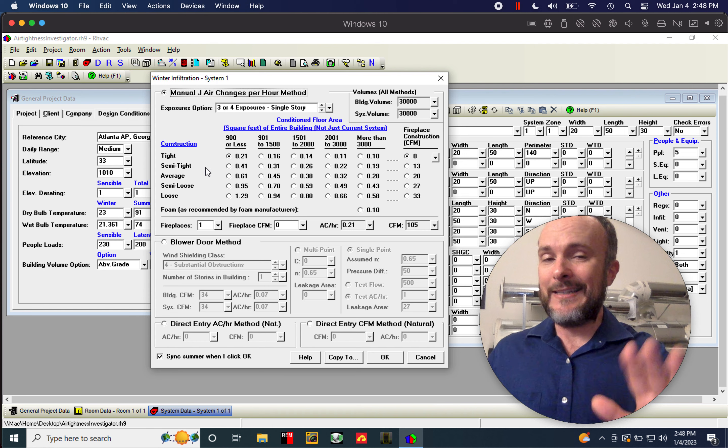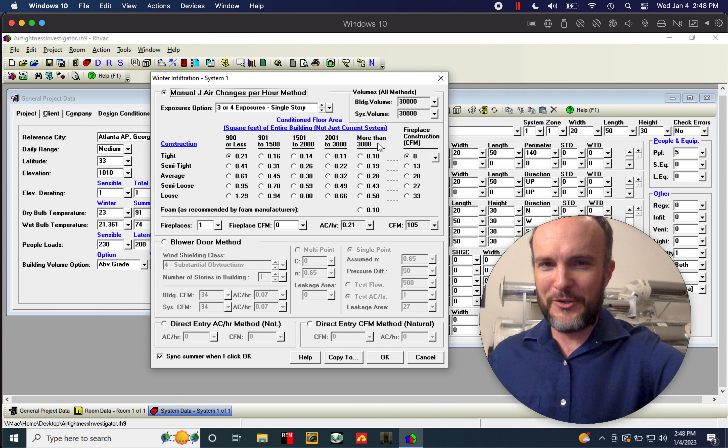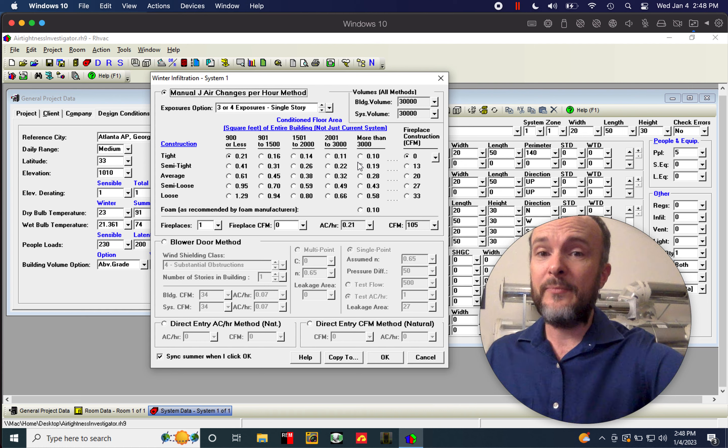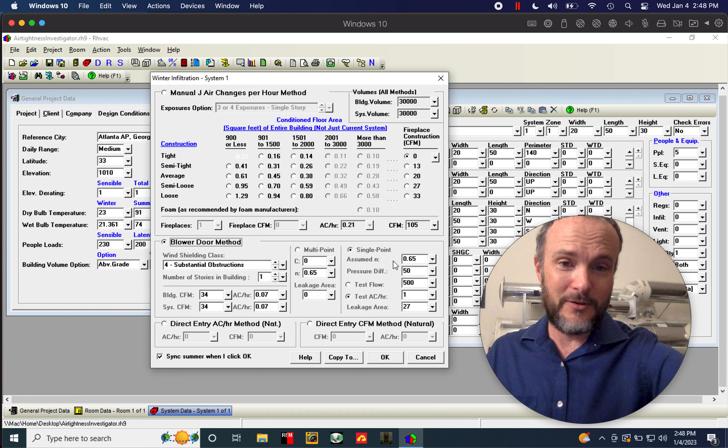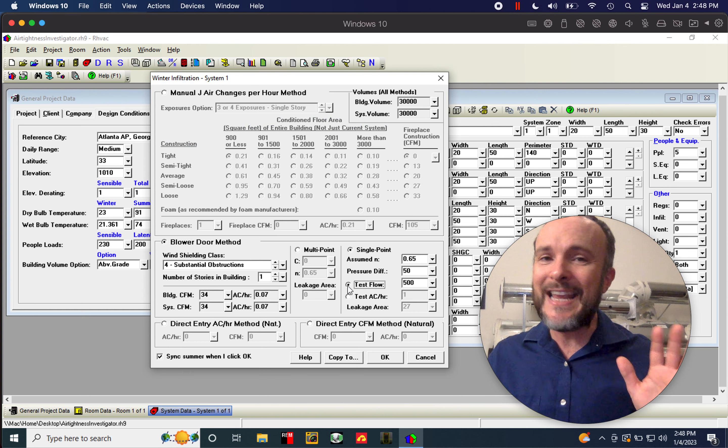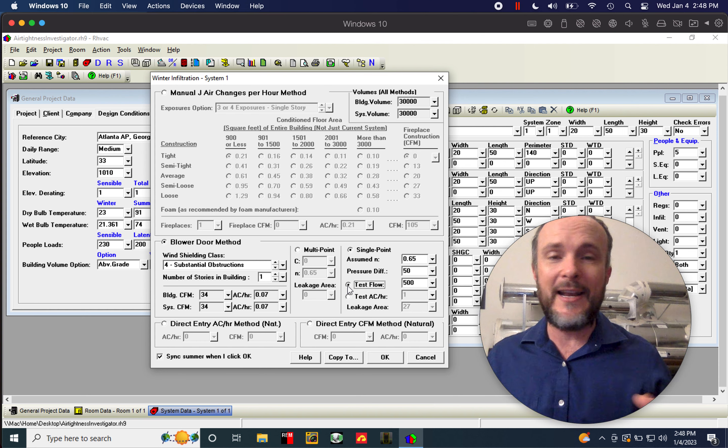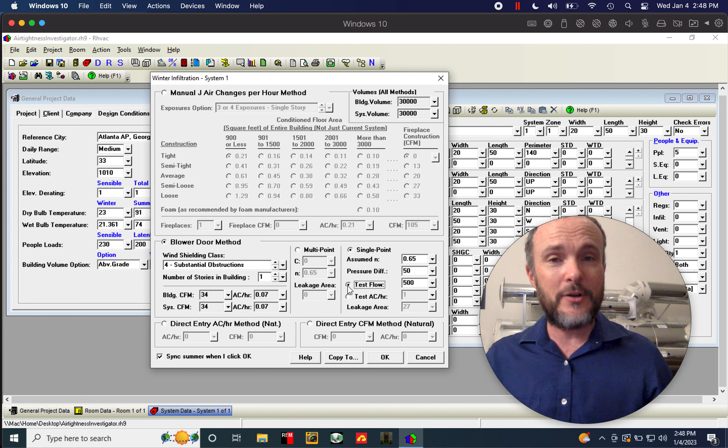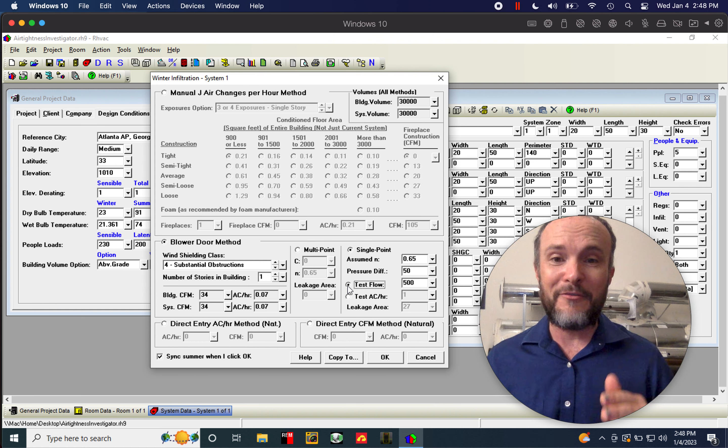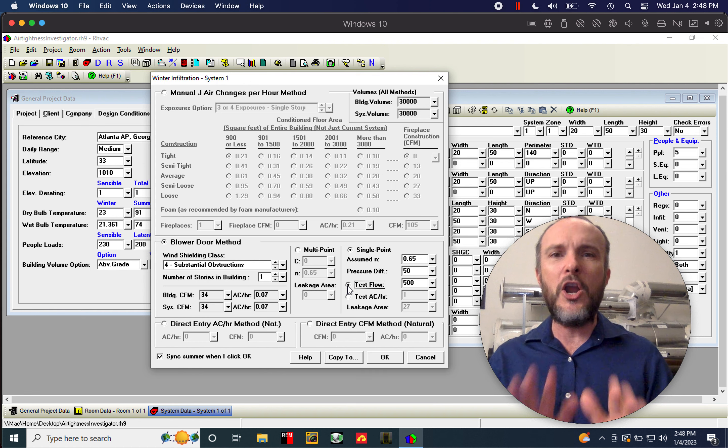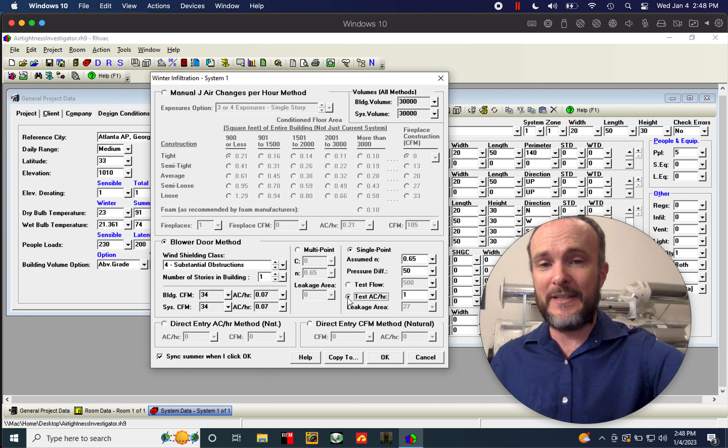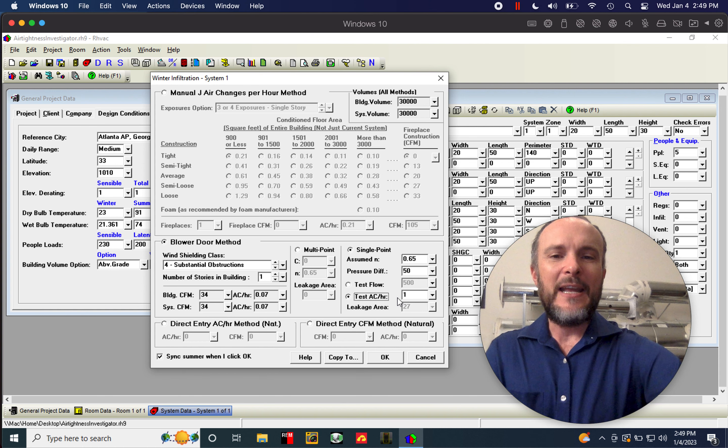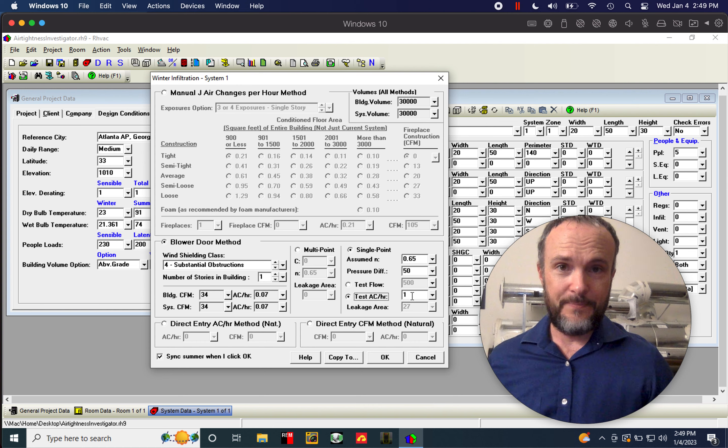It's these values in Elite, that you also have to select based on the square footage of your home. And so to show you how this works when I do it, we're going to go down here and look at Blower Door. All you have to do is you come over here and you can either put the test flow, which is the CFM 50. And if you want to know how to run a Blower Door test, I have a one-day training that's online. It includes an hour of coaching with me. You can even get certified if you want to challenge the exam. I'm linking on screen now for that if you want to check that out. But you should know, if you're building a home, what CFM 50 you're shooting towards. The ACH 50, or AC per hour, ACH 50 is what we call that, is mandated in code, in energy code.